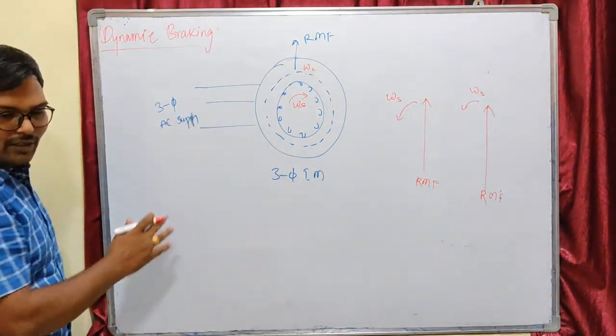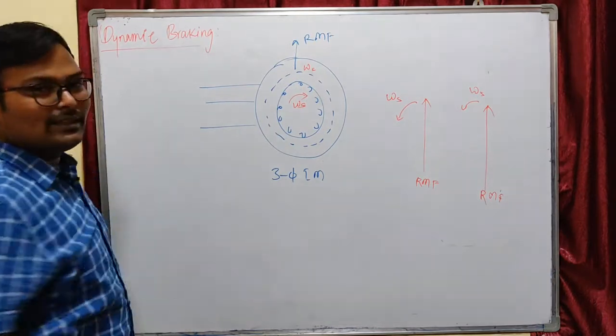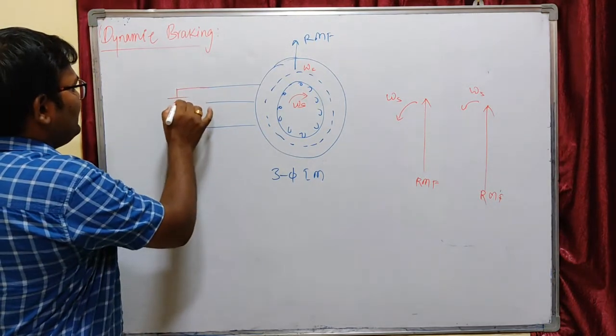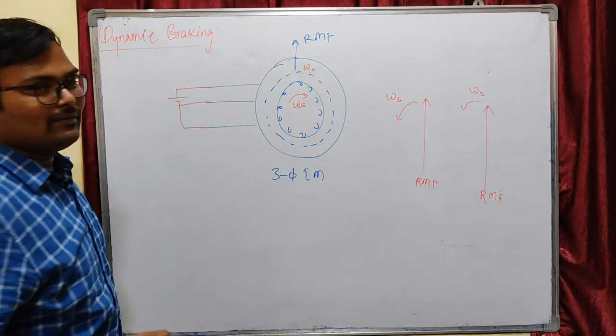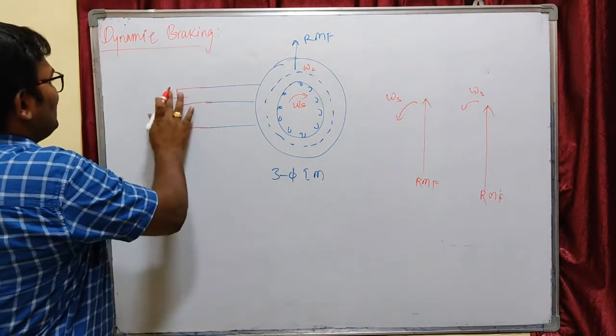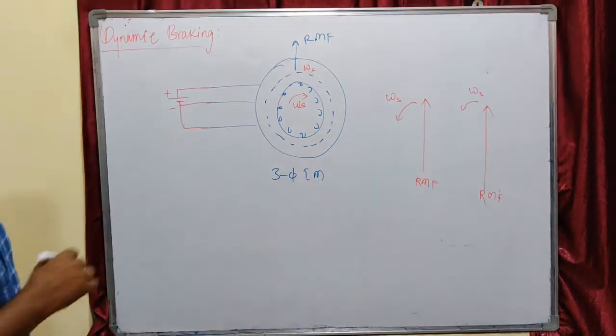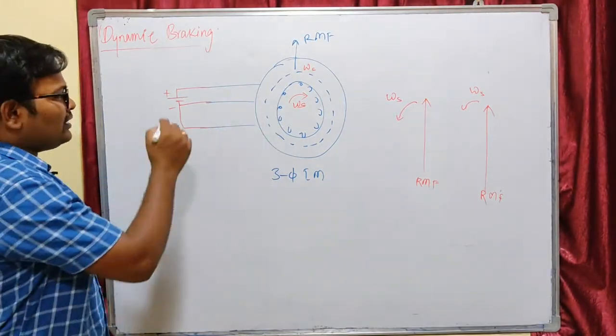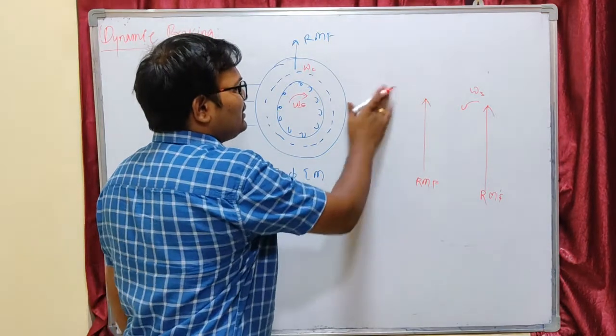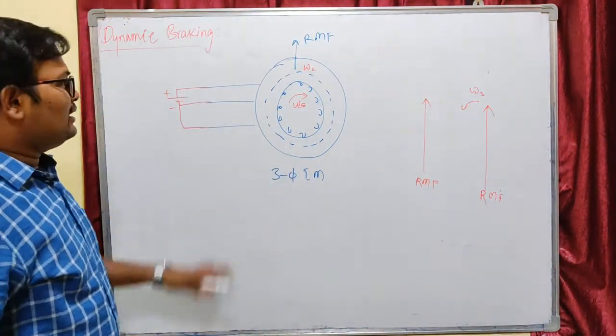In dynamic braking, we disconnect the stator from the AC supply and apply a DC supply to the stator — one positive terminal to one phase and two phases connected to one negative terminal. Initially there was a rotating magnetic field, but now with DC supply, it will be a unidirectional magnetic field. That means there will be no rotation in the magnetic field due to the DC supply.